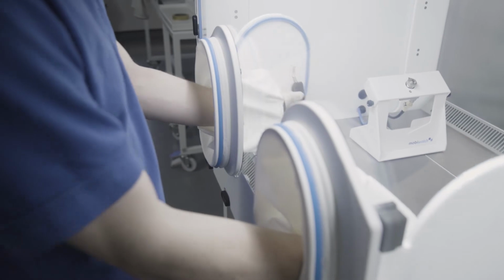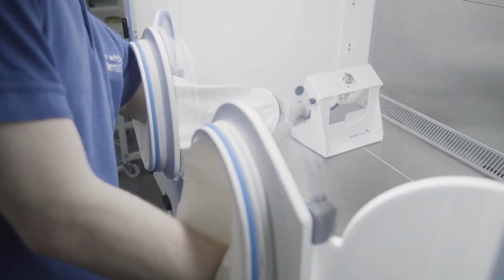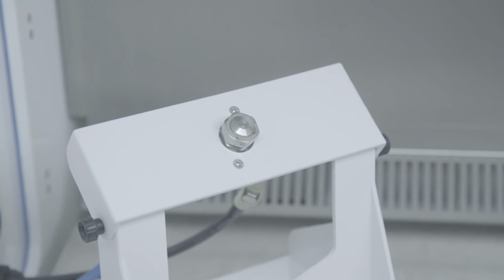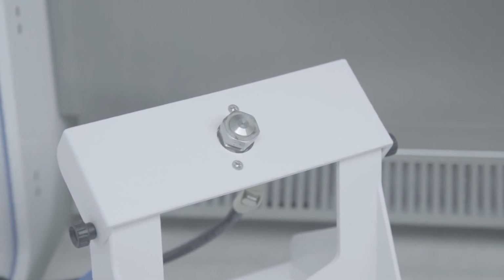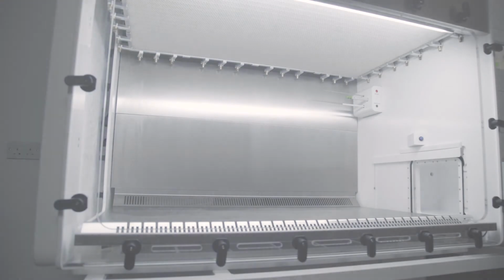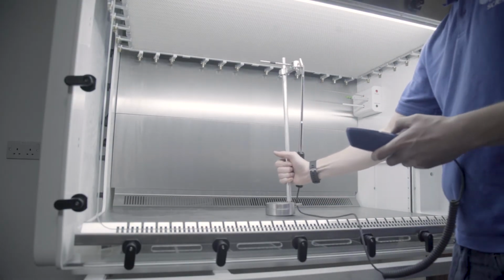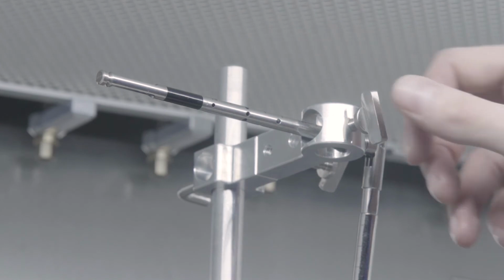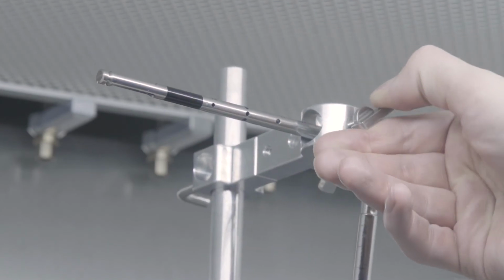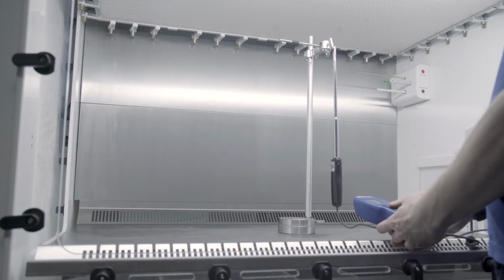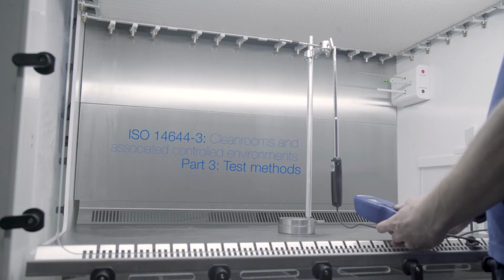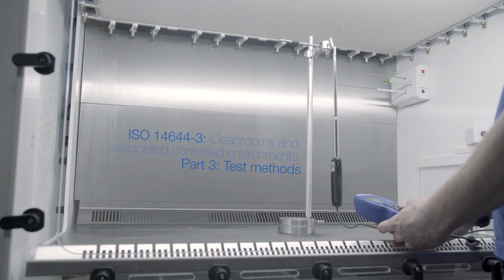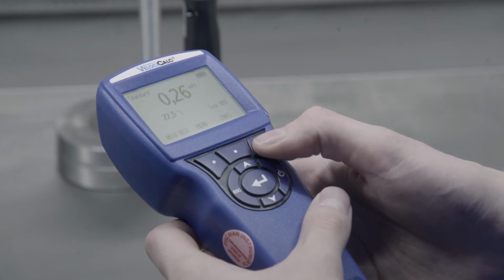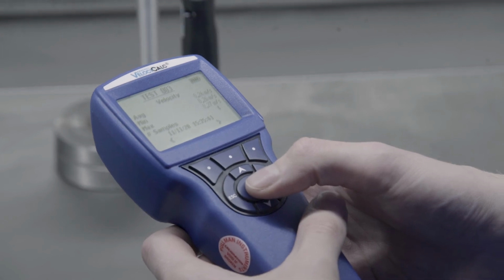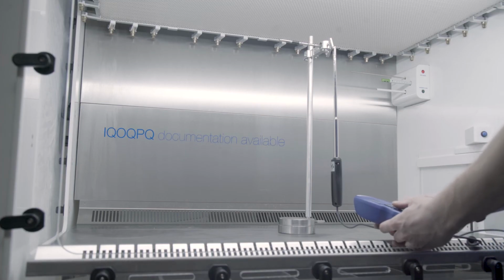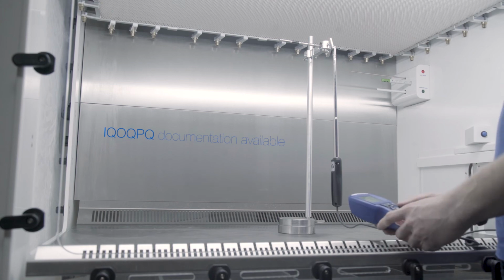We've carefully tested and selected the equipment and method best suited to this specific workstation, and the complete solution is available to purchase as an option. Before leaving the factory, all A135 GMP anaerobic workstations are validated to ISO 14644-3 through dispersed oil particulate integrity testing and airflow uniformity testing. Don Whitley Scientific also offers installation qualification, operational qualification, and performance qualification documentation and services.